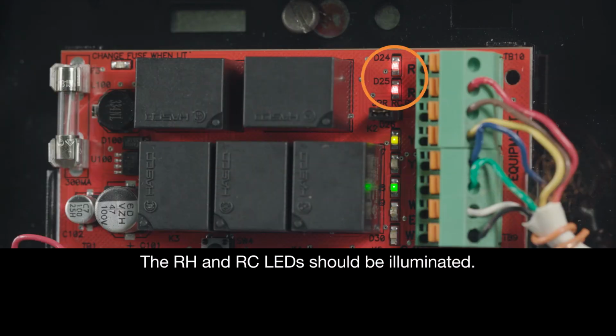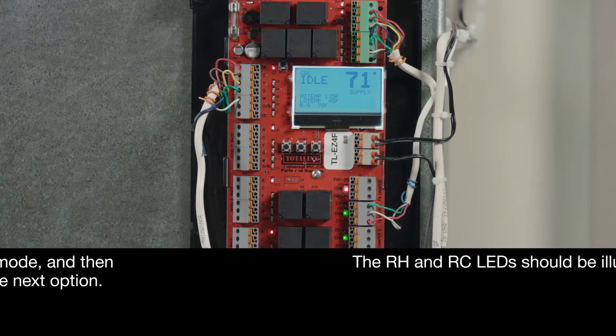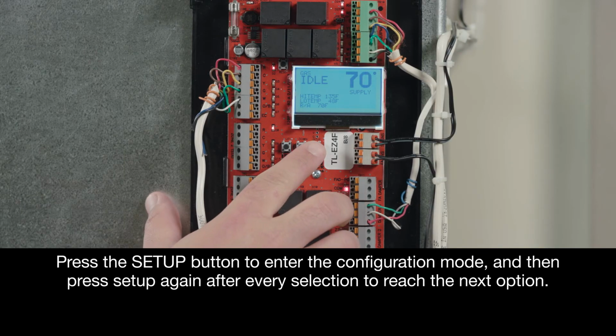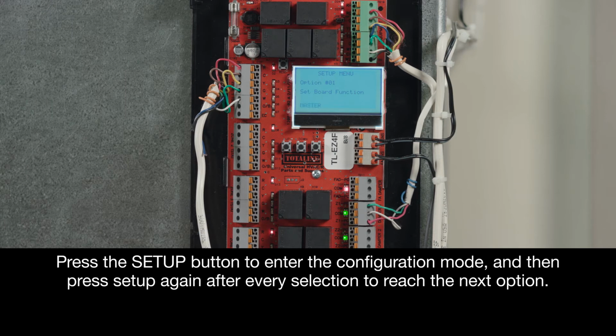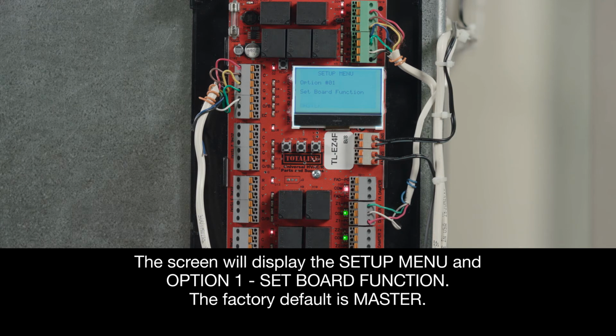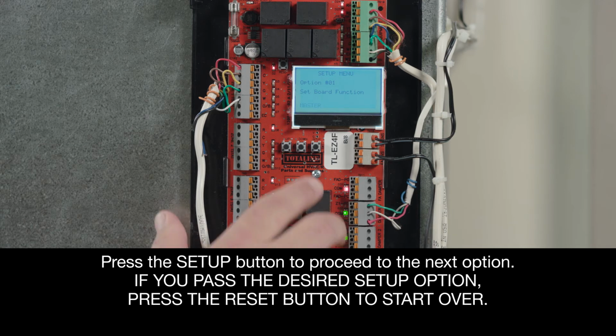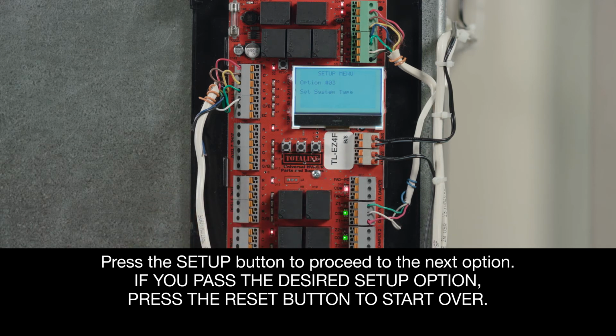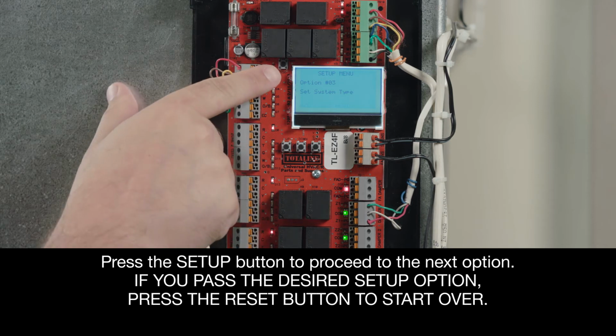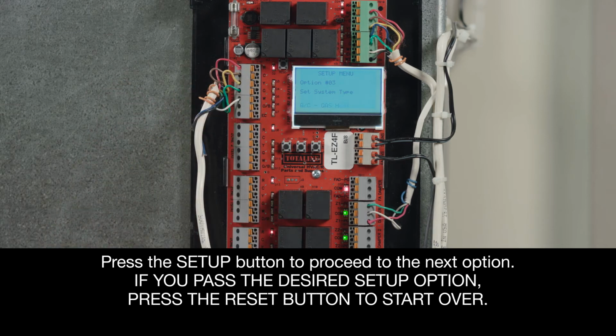Now that all wiring for the thermostats, zone dampers, and equipment is complete, it's time to configure and set up the unit. We'll do a setup for an AC and gas furnace system. At this point, the RH and RC LEDs should be illuminated. Press the Setup button to enter the configuration mode, and then press Setup again after every selection to reach the next option. The screen will display the Setup menu and Option 1, Set Board Function. The factory default is Master. Again, press the Setup button to proceed to the next option. If you go past the desired setup option, press the Reset button to start over.